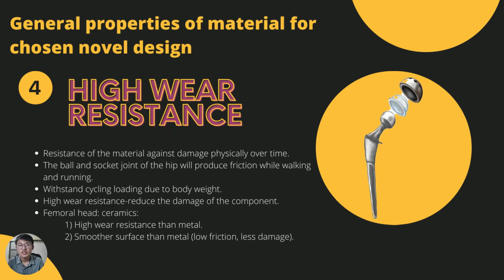In addition, the device should have high wear resistance. Wear resistance is the resistance of the material against physical damage over time. The ball and socket joint of the hip will produce friction while walking and running. Ceramics are used to make the femoral head because ceramics have a higher wear resistance than metals. They can withstand cyclic loading due to body weight better.